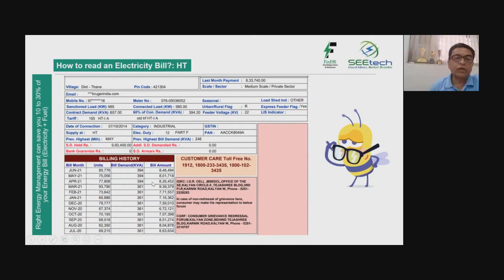So whether you consume or not, you will have to pay for 394 kVA. Where does this 394 come from? It is actually 60% of 657. So this particular company is paying 60% of contract demand, whereas their actual consumption is less. This is till April; it was till March basically 55%, so according to that they were paying 361, and now they are paying 60%, so that is 394.